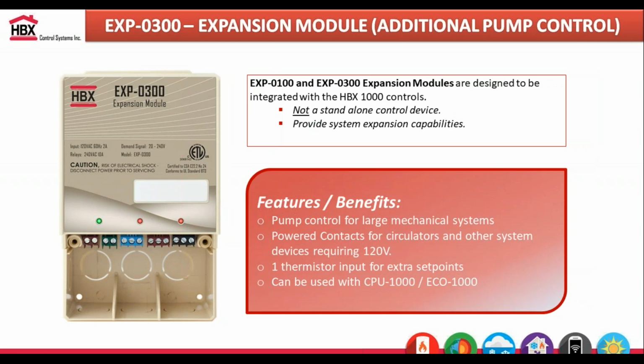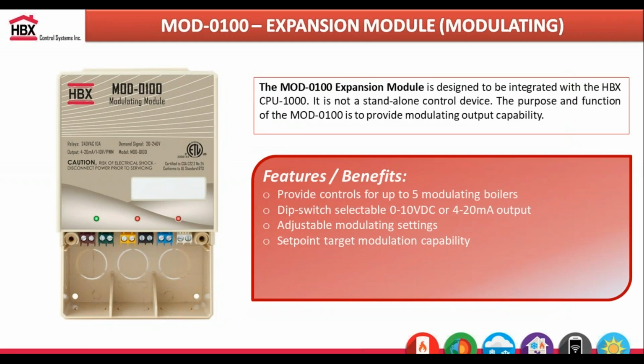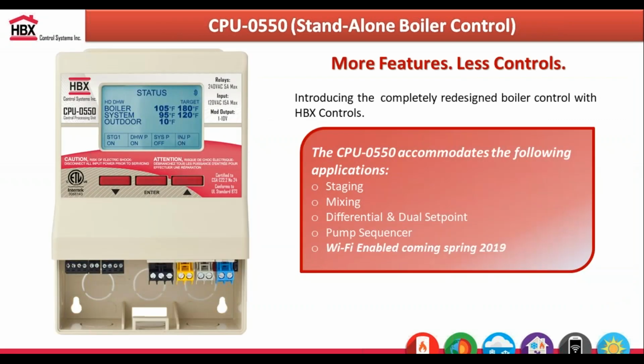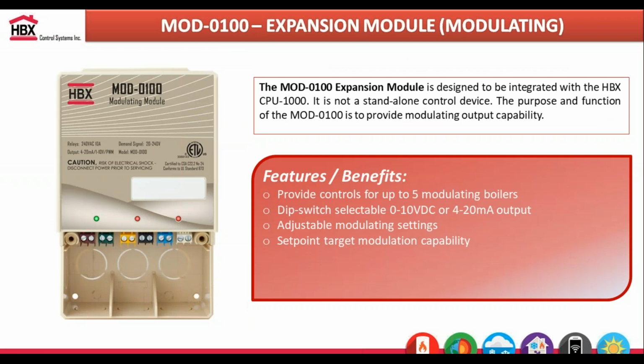We do have an expansion module for those pumps as well, so if you wanted to control more than 3 pumps, that's when you would add on our EXP300, and again, we have 120 volts coming out of these already. If you want to modulate devices, this is where you want to add on our Mod 100. We can do a maximum of 5 modulating devices with the 1000 controller. Each Mod 100 gives you the ability to do 2 modulating devices, to a maximum of three units. On that third unit we're only able to do 1, for a total of 5 modulating devices. We can do a 0 to 10 or a 4 to 20 mA output with the Mod 100, and it's just DIP switch selectable on the back of that expansion module.